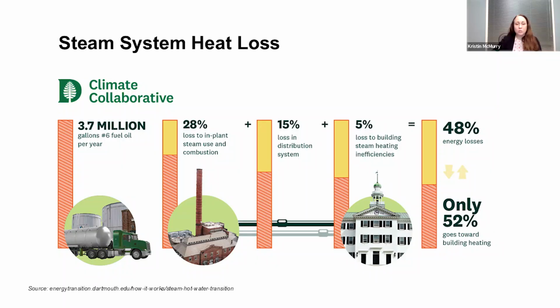So you're going to lose a pretty significant amount of heat there. And the 15% shown in this example could be higher, I've seen 27%, it can be pretty substantial. And then within the building you have some steam inefficiencies, and overall you lose 48% of what you put in. So if you looked at the COP, we usually talk about it for a piece of equipment, but you could look at it for the system as a whole. This system, I would say, has a COP of 0.52, so it's pretty low.